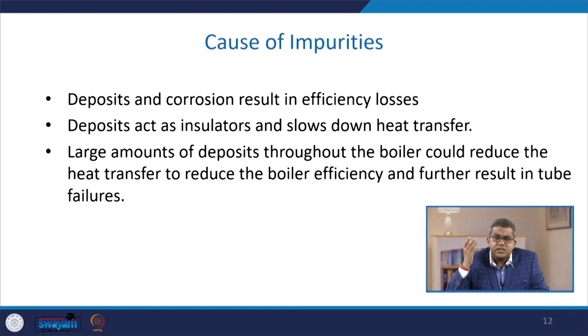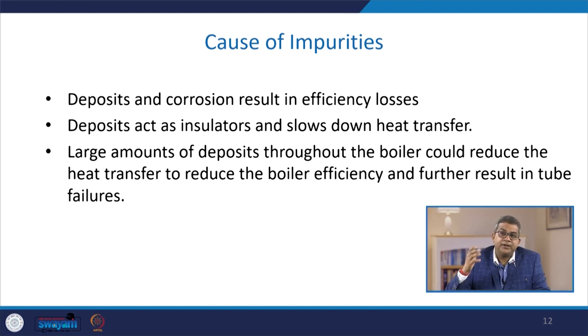There are various causes of impurities. Deposits and corrosion result in efficiency losses; deposits act as insulators and slow down heat transfer, ultimately reducing the energy efficiency and performance of the boiler. Large amounts of deposits throughout the boiler could reduce heat transfer, reduce boiler efficiency, and result in tube failure. Tube failures have two effects: the efficiency and performance of the boiler go down, and the boiler may create a safety hazard.